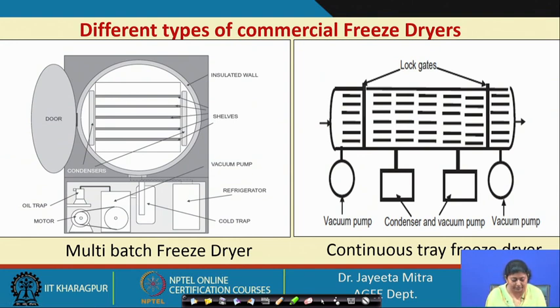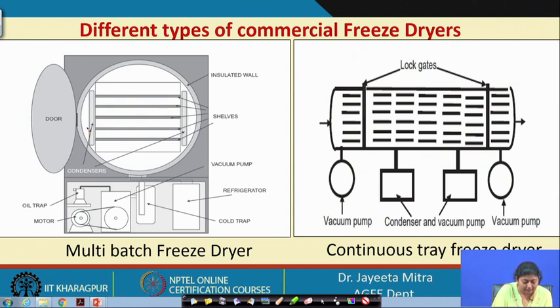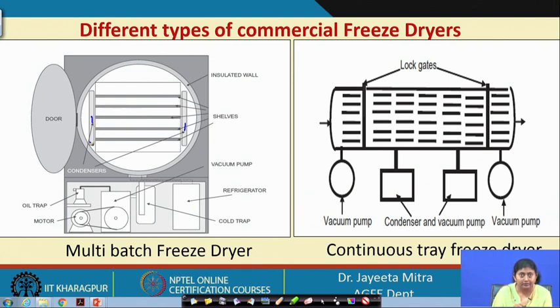Different types of commercial freeze dryer: the first is the multi-batch freeze dryer. It has insulated walls so that all heat supplied to the frozen layer is used for sublimation of ice to vapor, without heat leakage. These are the shelves. There is a condenser on both sides — as vapors come out they go to the condenser and form ice crystals. There is a vacuum pump oil trap, a motor, and a refrigerator serving two purposes: lowering the shelf temperature to bring the material to the freezing point, and keeping the condenser temperature low enough so vapor can be converted to ice.